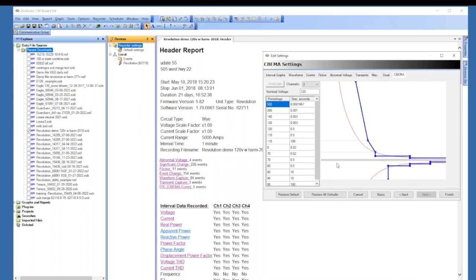But in general, the gray is your plus or minus 5%, and then you can see it can go upwards of 500%. But these are very quick. So this is kind of broken into thirds. 1/3 of this is cycle duration, less than a cycle. So transients. 1/3 of this is about a cycle in duration, and then 1/3 of this is up to about 10 seconds. But they'll just be dots on there. And then there's a report on the CBEMA that will explain where these occurred and what voltage and things they came to. So we are creating a template.